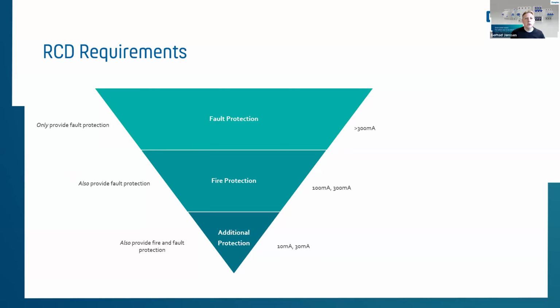To have fire protection, you need an RCD with at least 300 milliamp of residual current threshold, or better 100 milliamp residual current threshold. If you like to have or need more protection, if you need human protection, personal protection as we call it, you need at least 30 milliamp residual current protection in a device. Better go for 10 milliamp. If you have spa arenas or jacuzzis, for example, where water is involved, a 10 milliamp RCD makes the most sense to protect you and your beloved ones against electric shock.